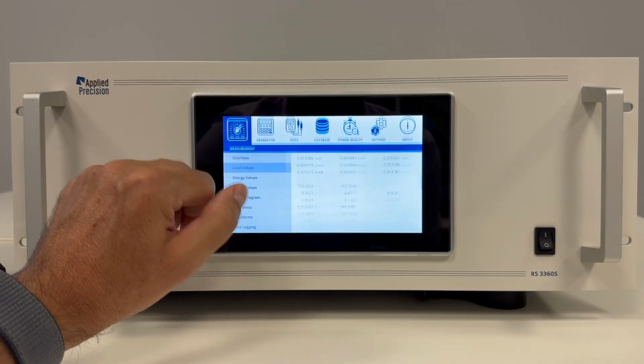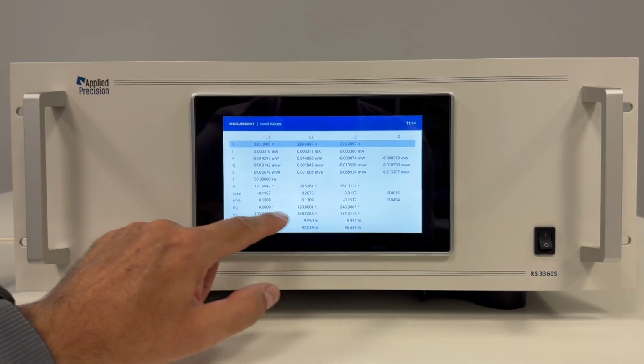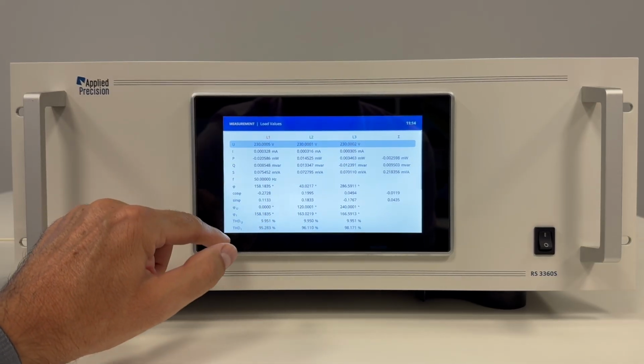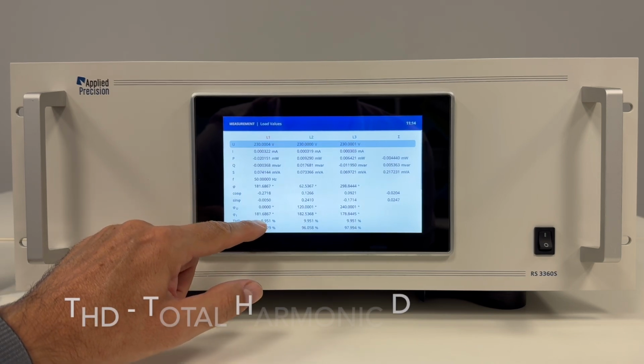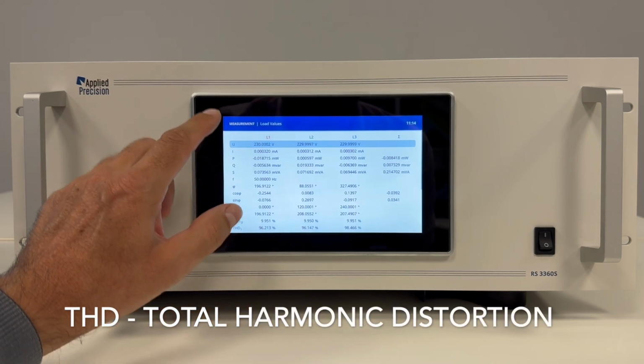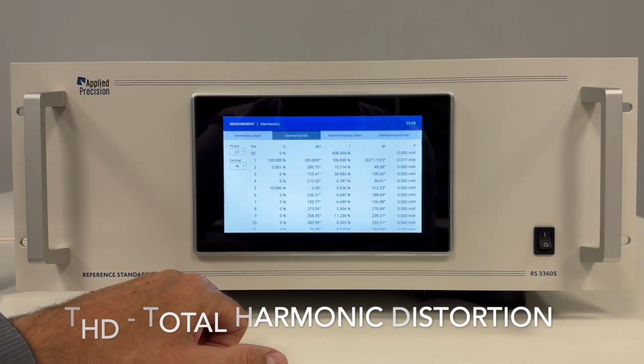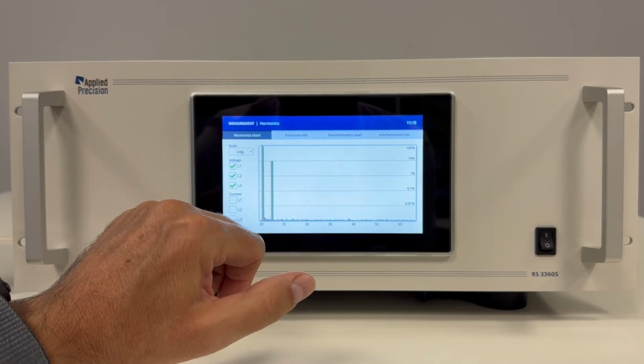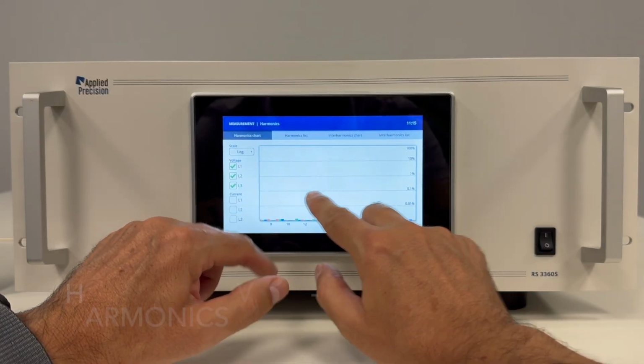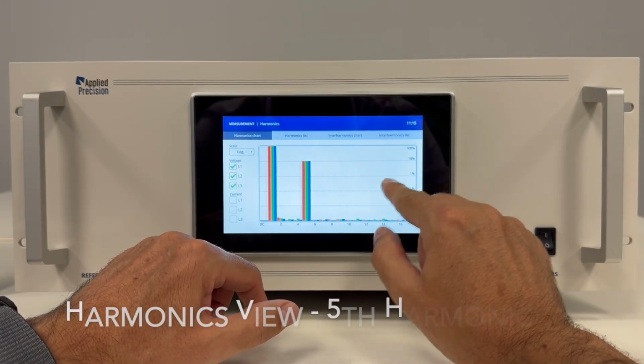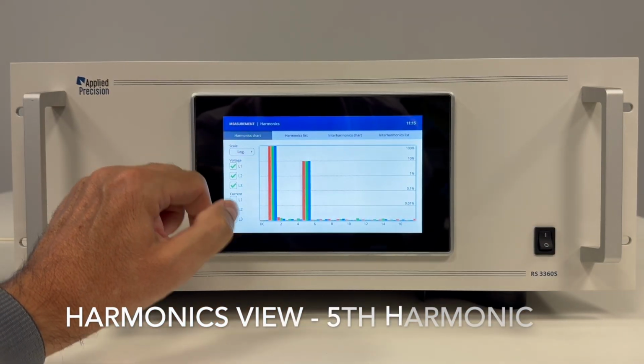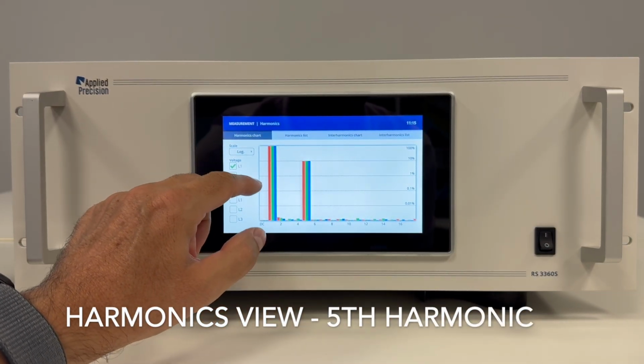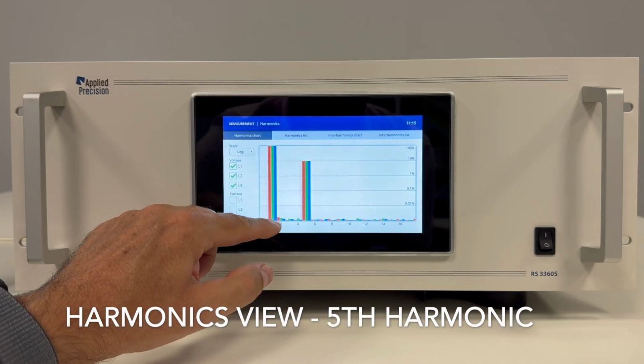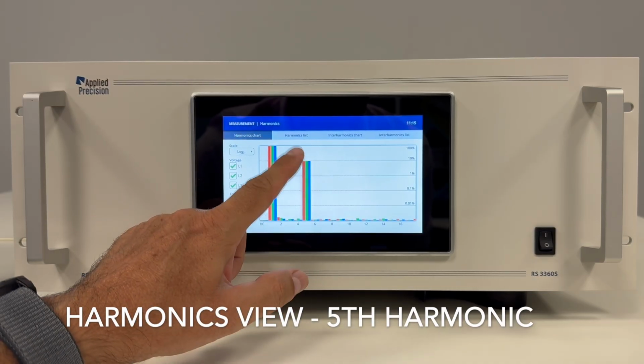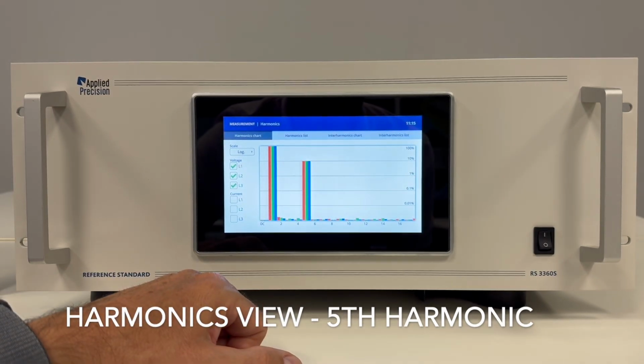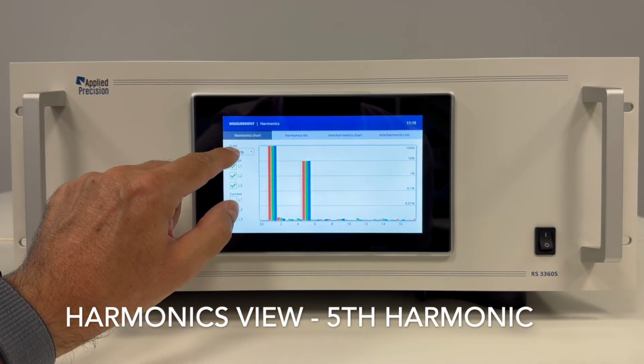We can go to the load values as well, or we can see more quantities measured in this screen, and we can see here THDU around 10%. Once we switch to harmonics and to the chart, if we zoom in, we have a logarithmic scale for the voltages. So we can see that at 100% we have the first harmonic, which is the fundamental, and at 10% of the scale we have the fifth harmonic.